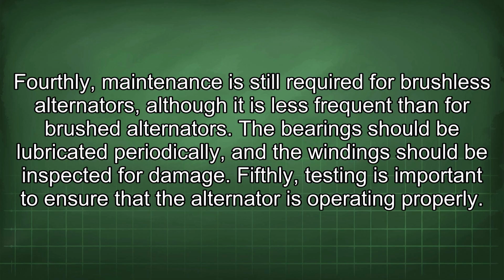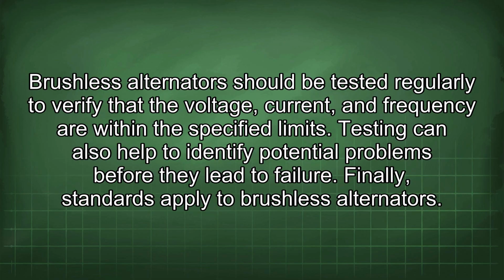Fourthly, maintenance is still required for brushless alternators, although it is less frequent than for brushed alternators. The bearings should be lubricated periodically, and the windings should be inspected for damage. Fifthly, testing is important to ensure that the alternator is operating properly. Brushless alternators should be tested regularly to verify that the voltage, current, and frequency are within the specified limits. Testing can also help to identify potential problems before they lead to failure.